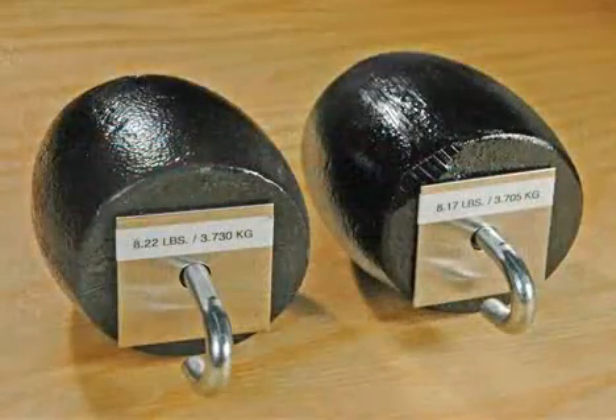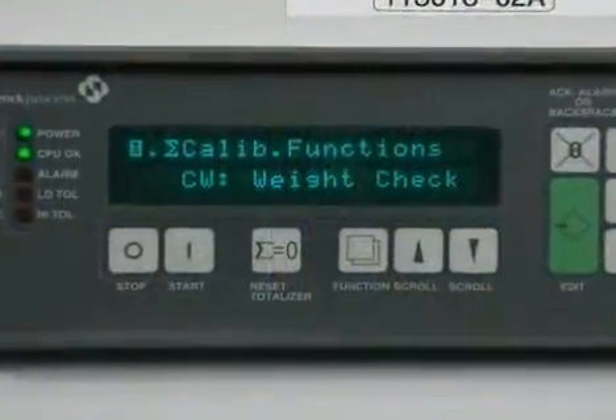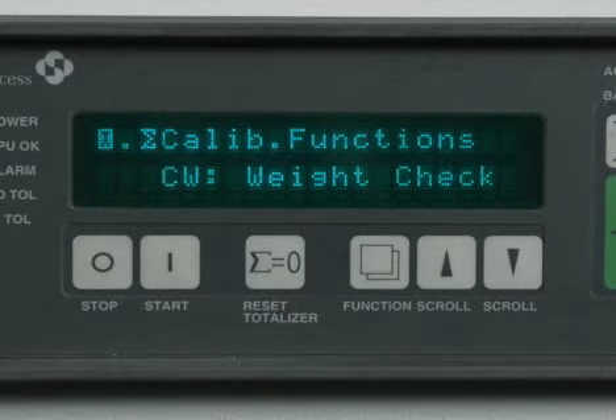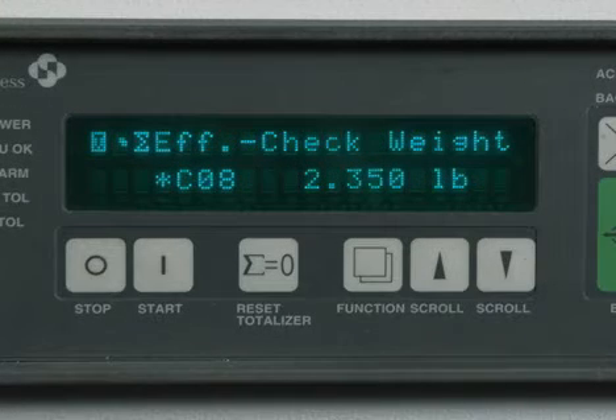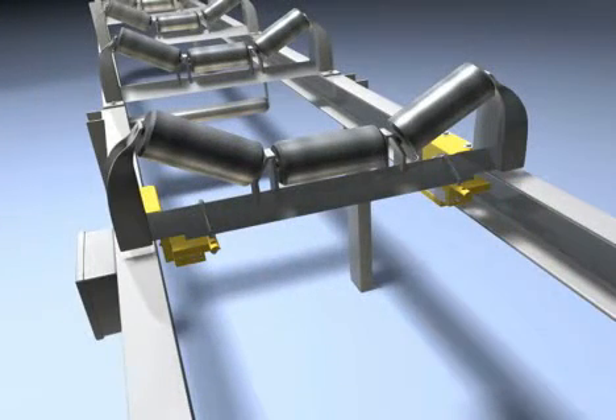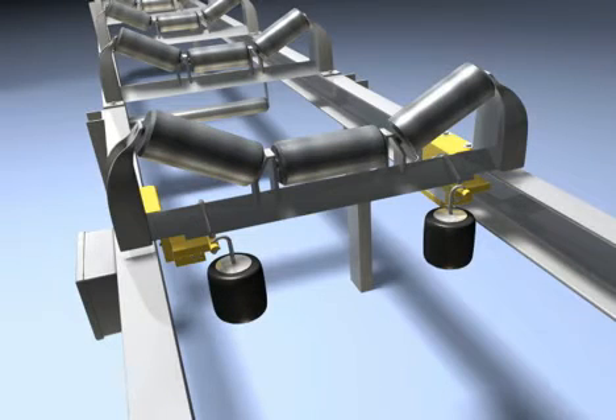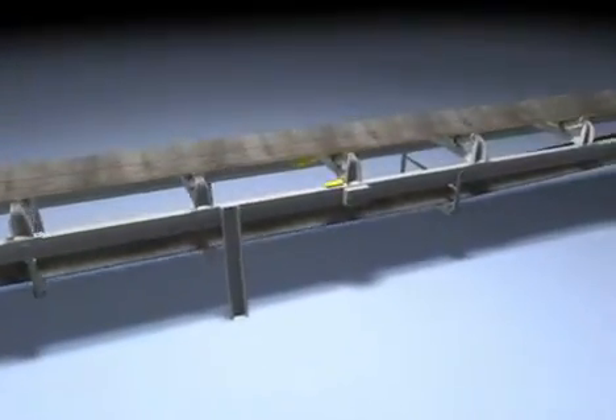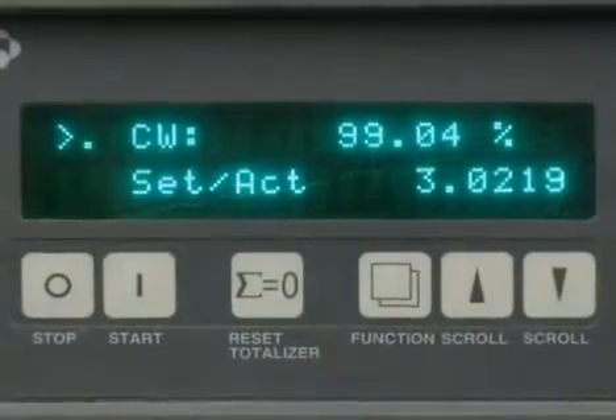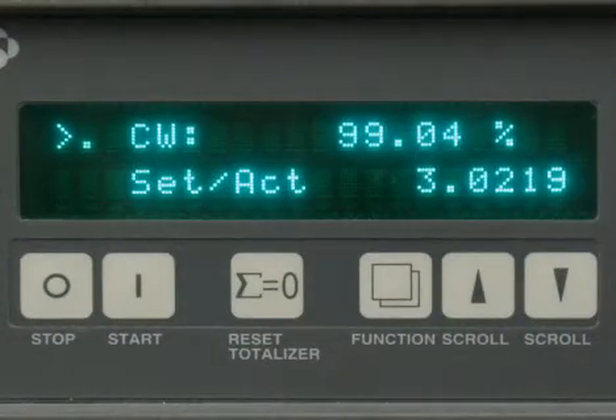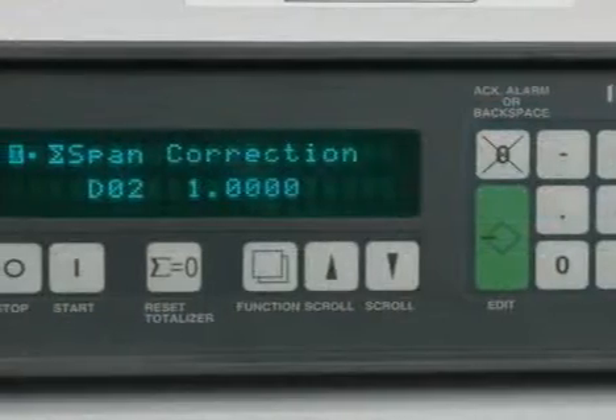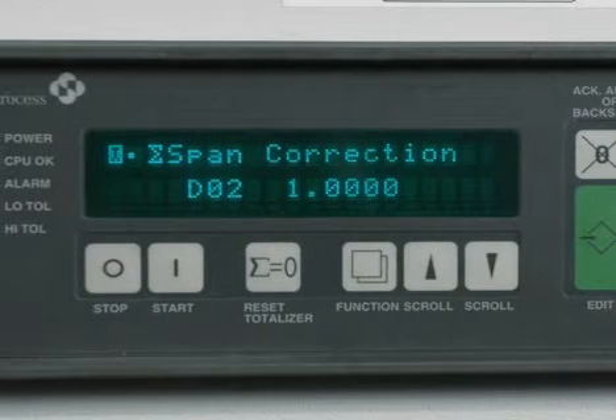The next part of the calibration process involves a set of check weights and the check weight calibration function in the calibration functions menu. Begin working with the check weights by entering their weight value into the system. The check weights can now be suspended from the weigh bridge, making sure that they have sufficient clearance to avoid contact with the belt. With the weights in place, run the system in volumetric mode and start the check weight calibration program. The program will supply you with a correction factor, which compensates for any inaccuracy of the load cell. Enter the span correction in the menu.